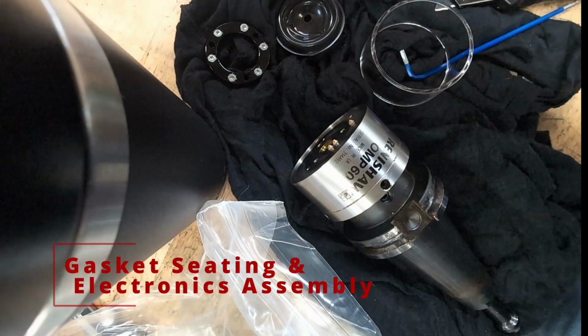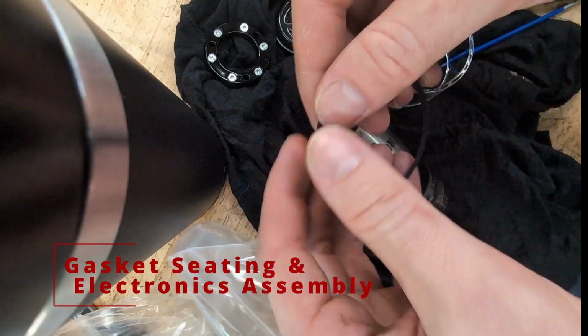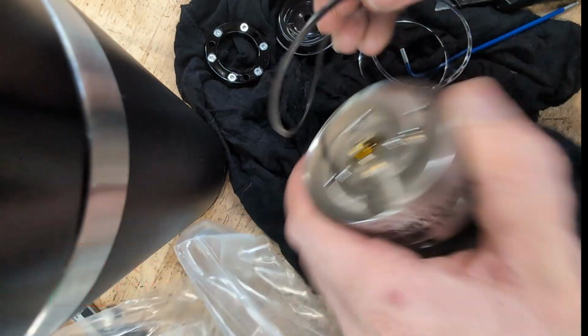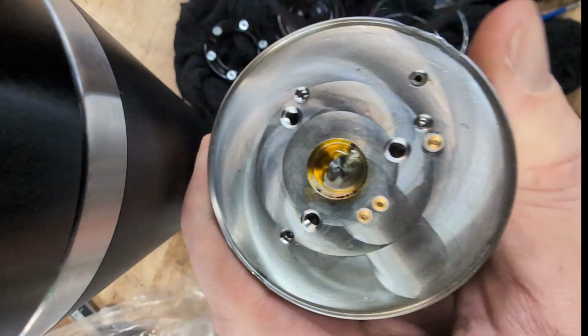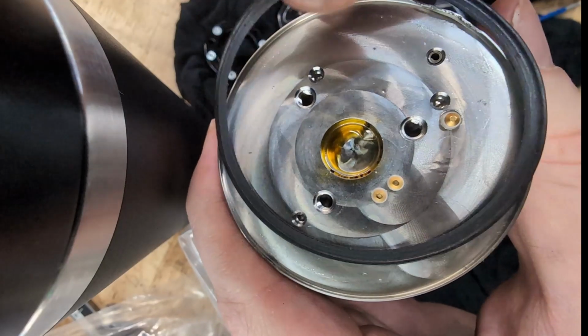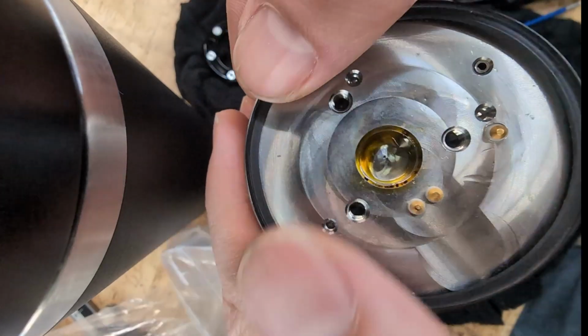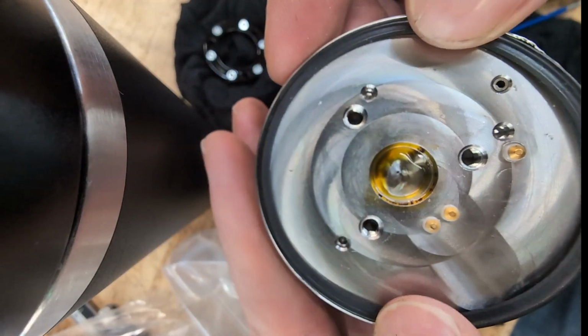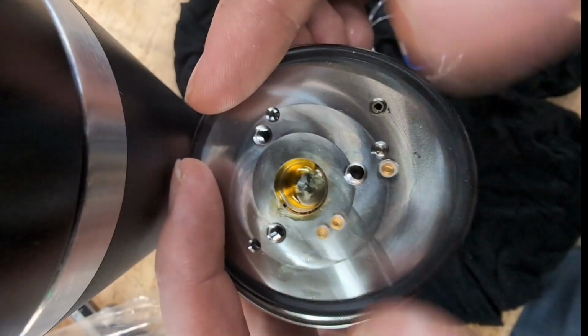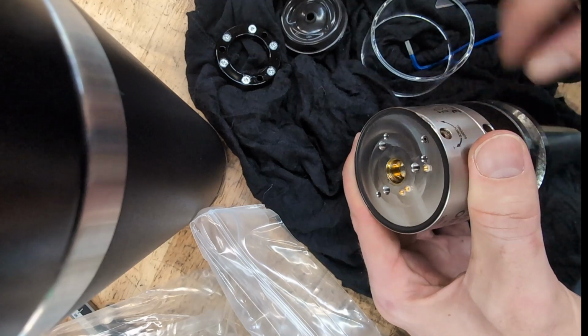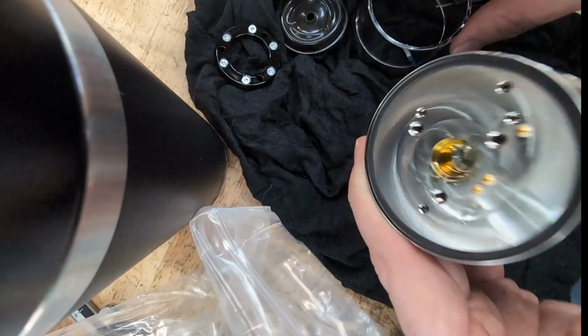Gasket seating and electronics reassembly. First, we seat the internal gasket that the glass seals against. Make sure both the metal surface and the seal itself are surgically clean. If a piece of grit or lint gets in here, pressurized coolant will find its way past and you'll ruin the electronics. Speaking of electronics, avoid touching the boards directly if you can.